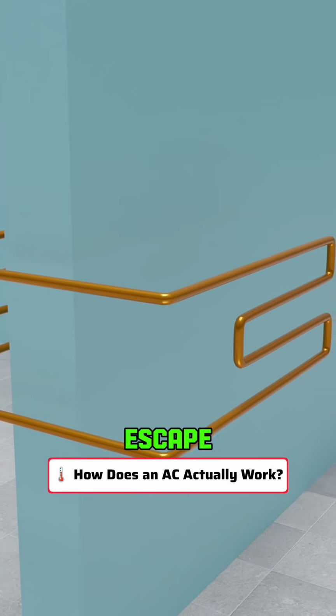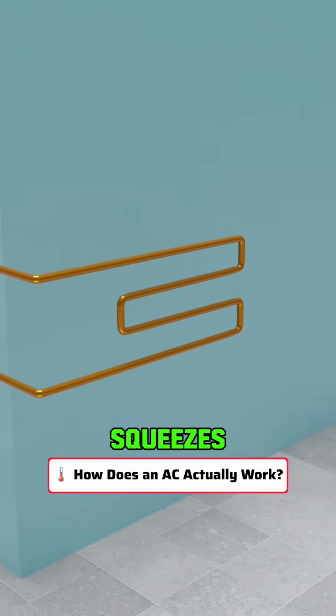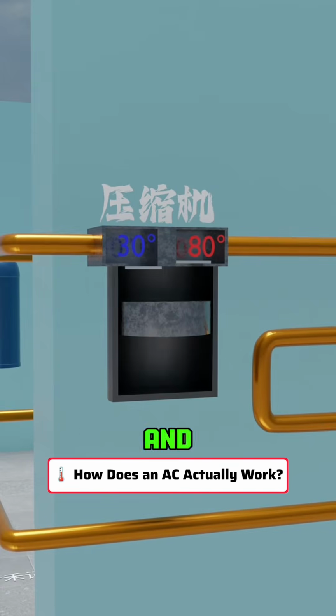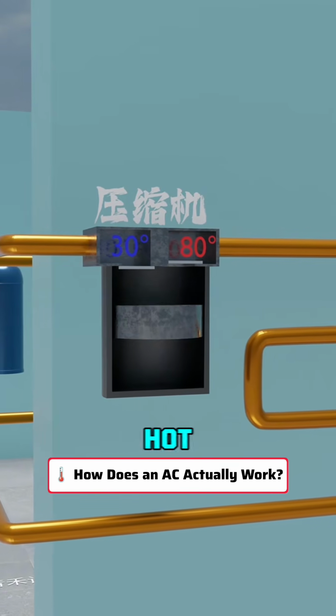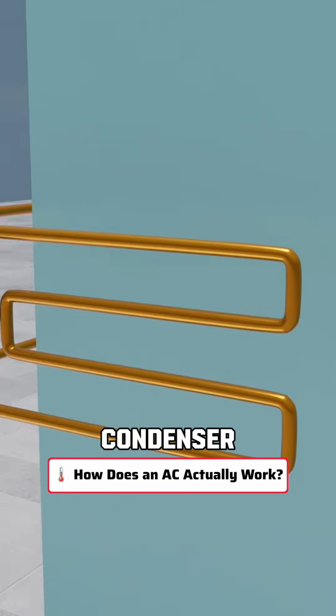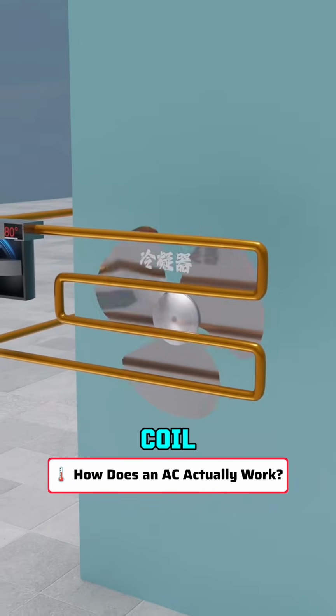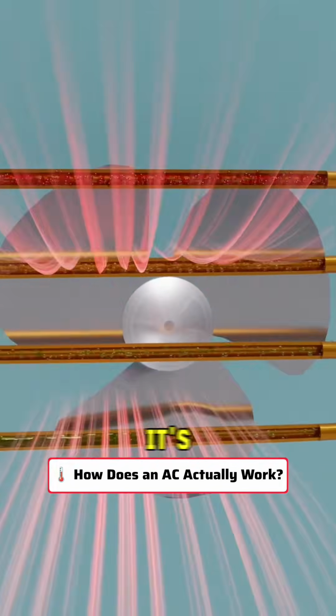Instead of letting it escape, you send it through a compressor. The compressor squeezes the gas, raising both its pressure and temperature. Since the gas is now extremely hot, it travels outside to a condenser coil. A fan blows air across the coil, carrying away the heat. As the refrigerant loses that heat, it changes back into a liquid, but it's still under high pressure.